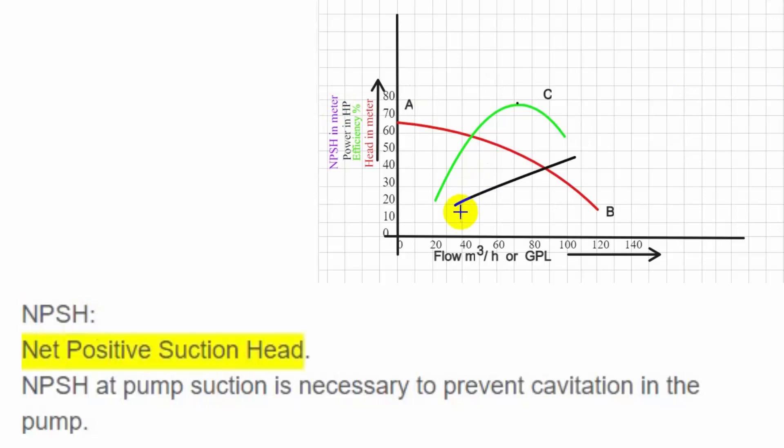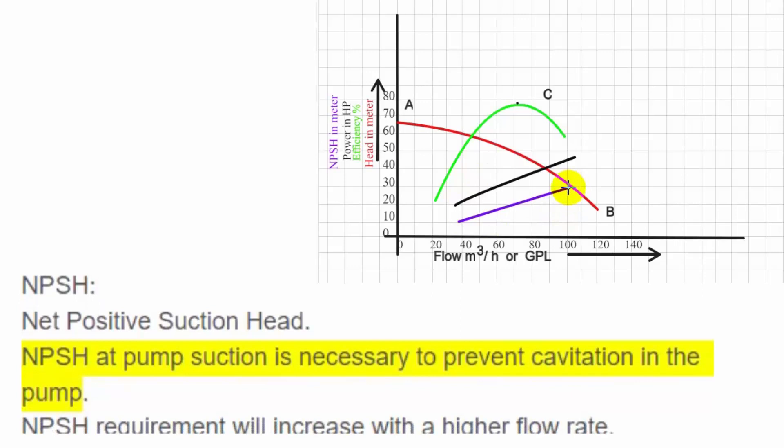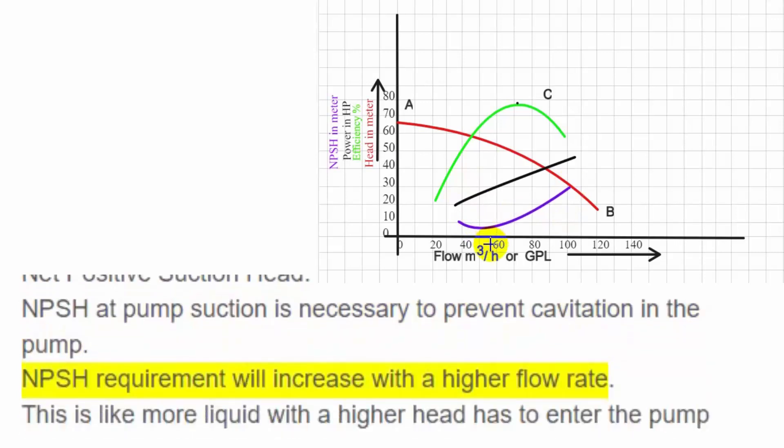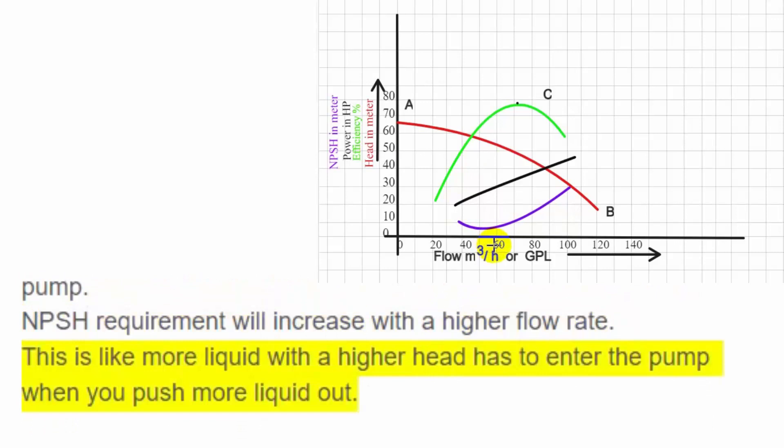NPSH - Net Positive Suction Head. NPSH at pump suction is necessary to prevent cavitation in the pump. NPSH requirement will increase with a higher flow rate. This is like more liquid with a higher head has to enter the pump when you push more liquid out.